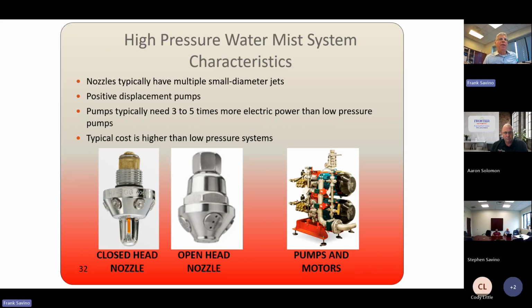So typical nozzles, these are high pressure water mist nozzles. This is what they look like, some of the characteristics. If you look at the nozzle all the way to the left, that's a closed head nozzle. That orange thing that you see there is the frangible element that heats up in a fire and then it breaks. And what happens is the water is discharged through these tiny jets that I'm pointing to here. I don't know if you see that. There's probably like 6 jets on that. And so the water mist comes out at a very high pressure out of those jets.